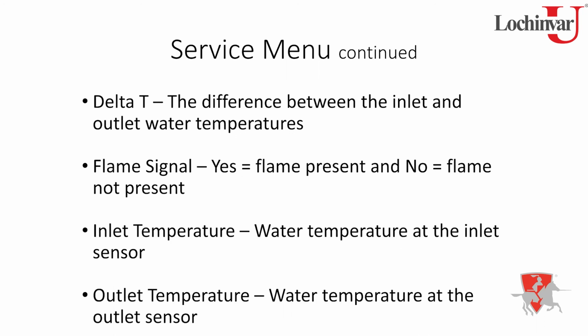First thing you're going to see is delta T. We talked about this earlier. Mm-hmm. Now, the manual says 10 to 14 degrees. And again, as long as you're within that range, you're probably going to be all right. That's ballpark. Yep. If you see something like 1, that's probably a red flag for something. More likely you're going to have other issues. Same thing if you saw a really high number. You're probably going to have other issues such as a high limit trip or something of that nature. So again, just keep that in mind.